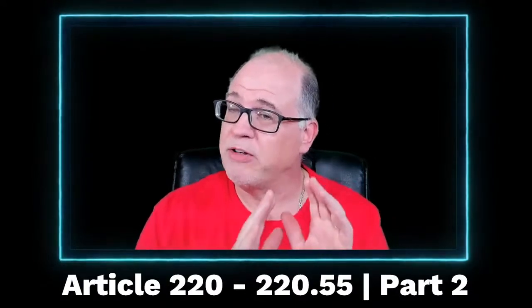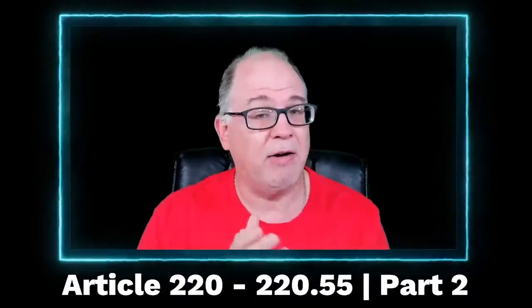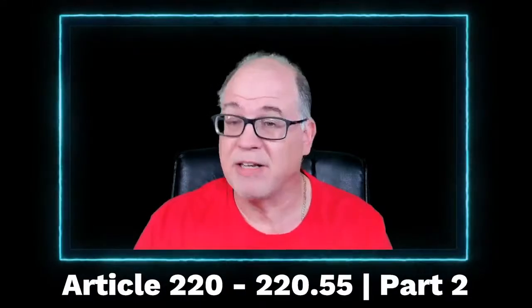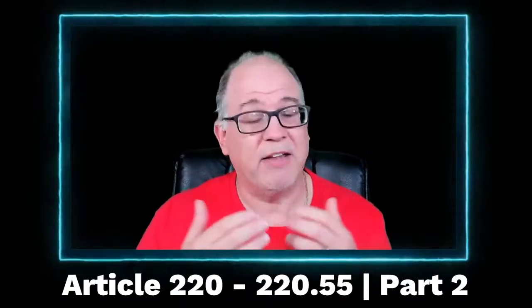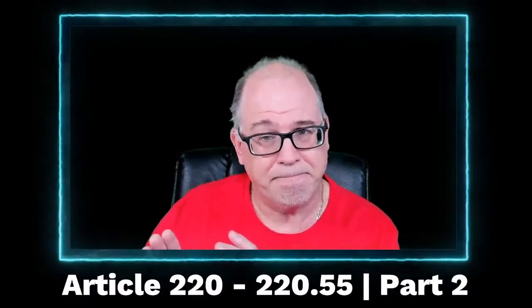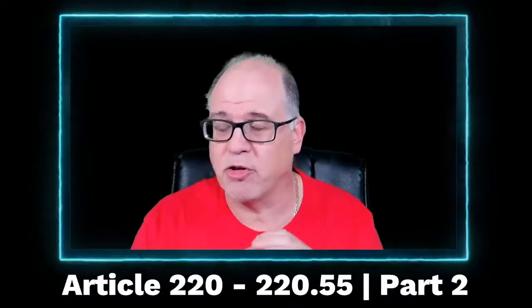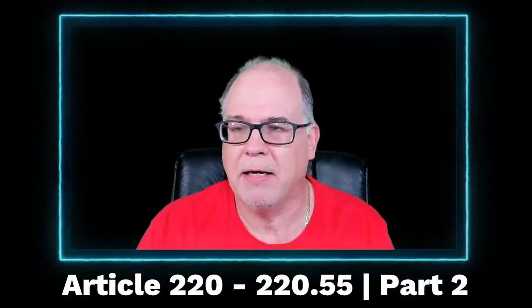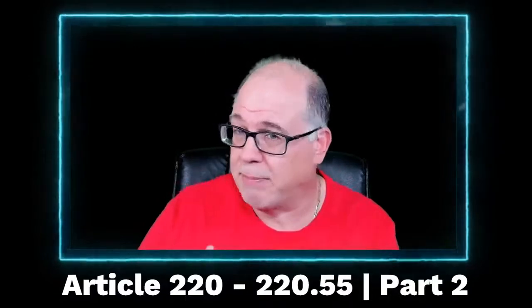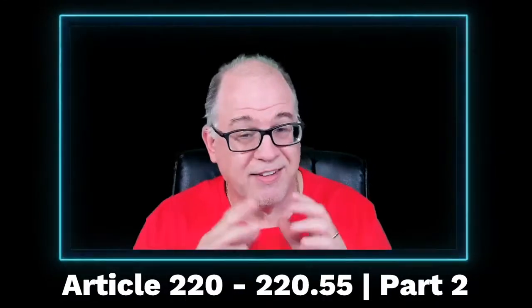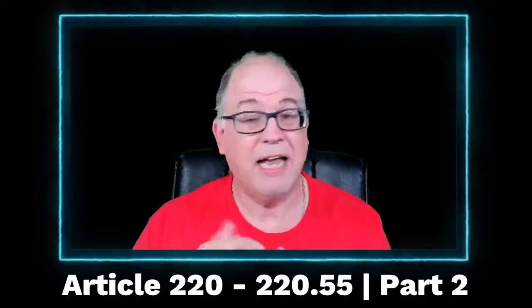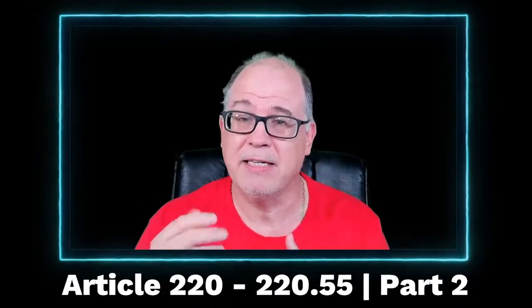Now, again, we talked about how to do branch circuits. In this part, we're going to get into calculating the loads using the standard method, which utilizes the 220.55 table. Remember, if it's the optional method, you just take the nameplate. If it's the standard method, you're going to use 220.55, and you might be using the standard method to size a feeder to an individual dwelling unit. You might be doing the optional method, but if you're using the standard method, you need to know all about 220.55 and the tables, as well as those notes that are underneath it.